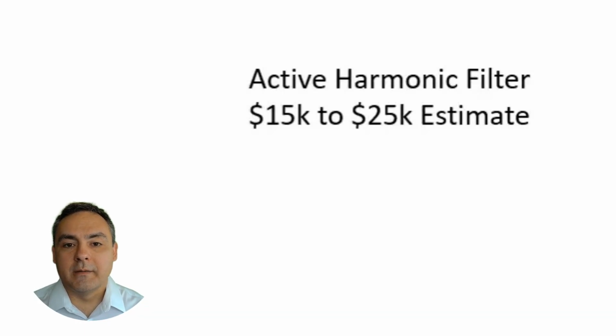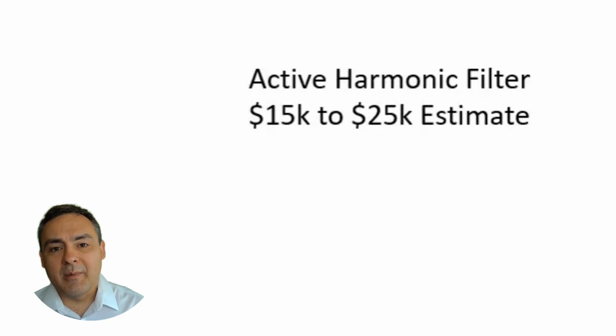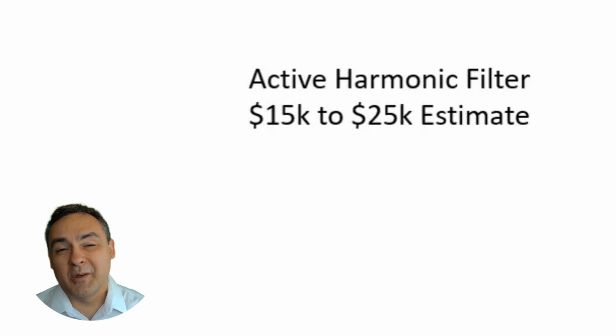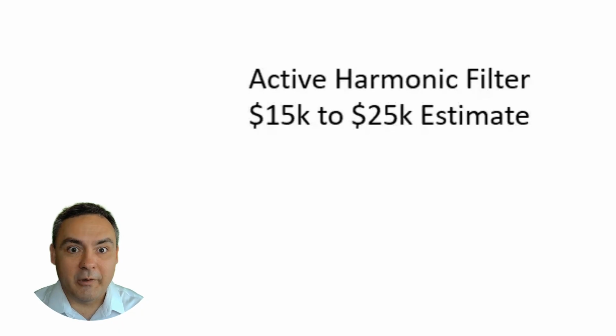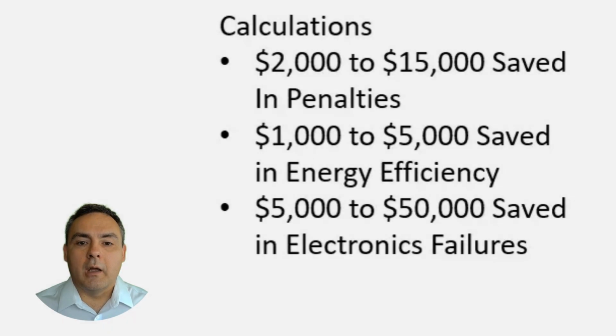Let's look at a mitigation investment example, that being our active harmonic filter. It might cost us $15,000 to $25,000 to install. Passive filters, like individually placed line reactors and filters, may lower the cost, but they may not cover power factor or dynamic loads, and they may not be feasible in our facility.